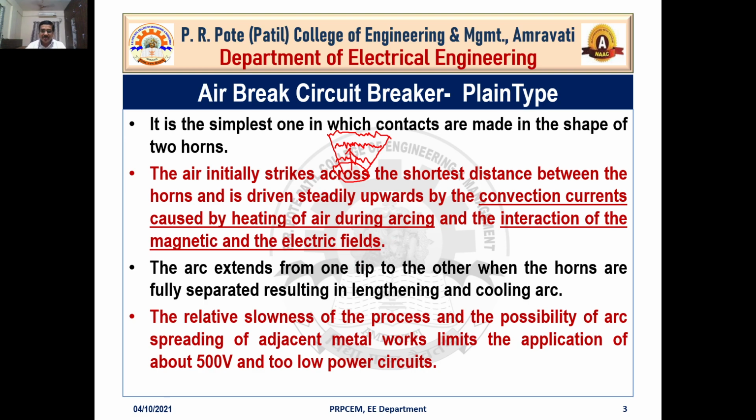Okay. Because the process of moving this particular arc from one position to another is very slow, that's why we are limiting this particular arrangement only to smaller-value circuit breakers. So that means you cannot use this circuit breaker for larger or high voltage categories, because this process takes time, and that will increase the fault clearing time inside the circuit breaker.